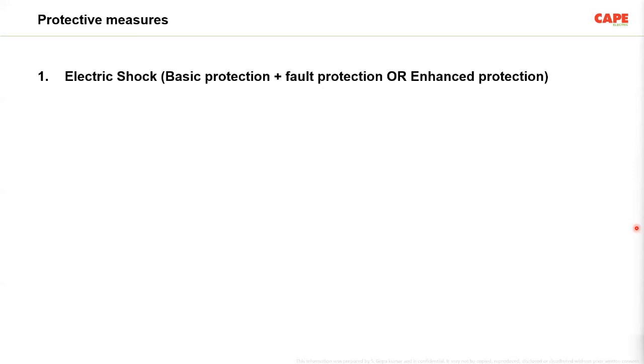So basic protection alone cannot provide you safety. You need basic protection and fault protection. Now, these basic and fault protective measures are selected based on the environment where you need safety. For example, some of the protective measures such as automatic disconnection of supply, double or reinforced insulation, electrical separation of one item of current using equipment, or extra low voltage. Actually, these safety measures are the ones which can be implemented in a general location, that means where common people are available.